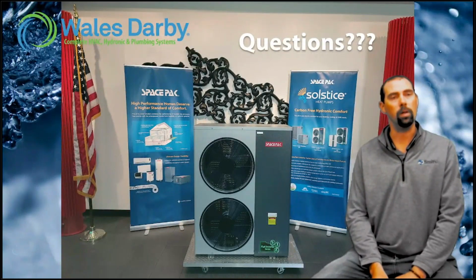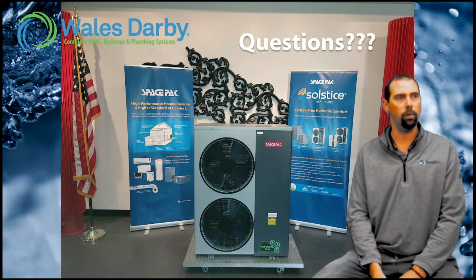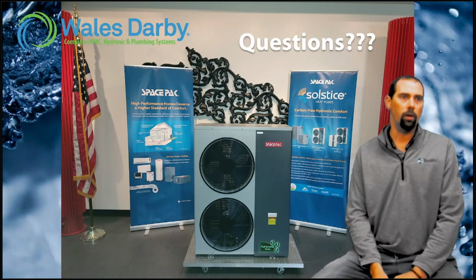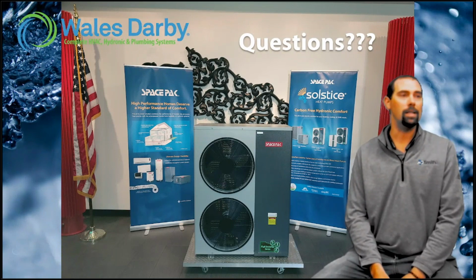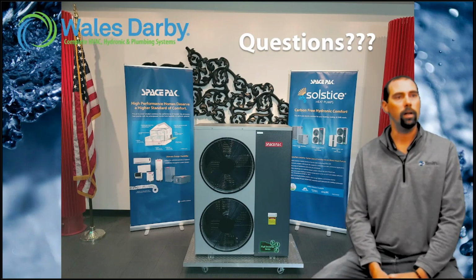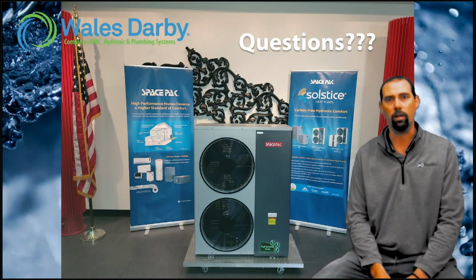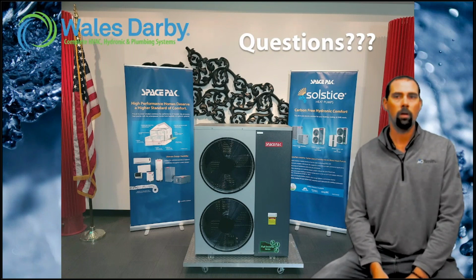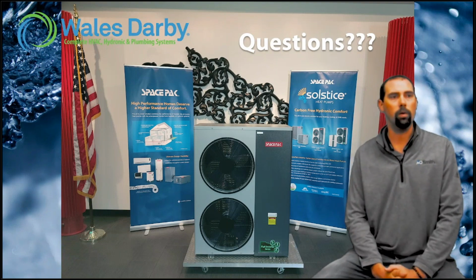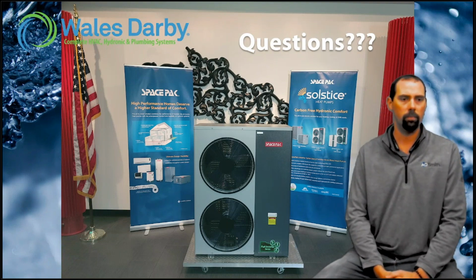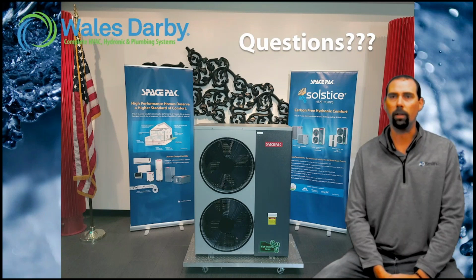That's the max, so we don't have a long distance we can do, and that's one of the cons, I guess you can say, of refrigerant. We have these limitations on the compressor and everything else, where in monoblock systems we have no limitations, it's creativity and size of the pump, which we can do all day. But yeah, that's gonna be 35 feet, still a decent distance. You're putting that thing outside and coming through a wall and going into a mechanical room, definitely see a lot of good applications for that.